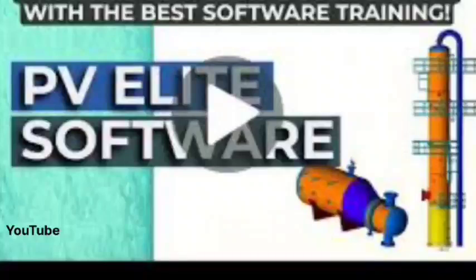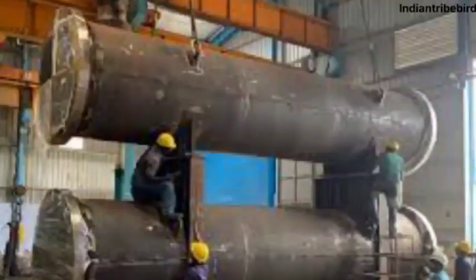I think in PV Elite there is always a second option. Like when we design a stack type heat exchanger, we have to provide the wind area. But instead of providing a wind area, we can just put a double wind load multiplier. If we choose the double wind load multiplier, the wind and seismic load also decrease.